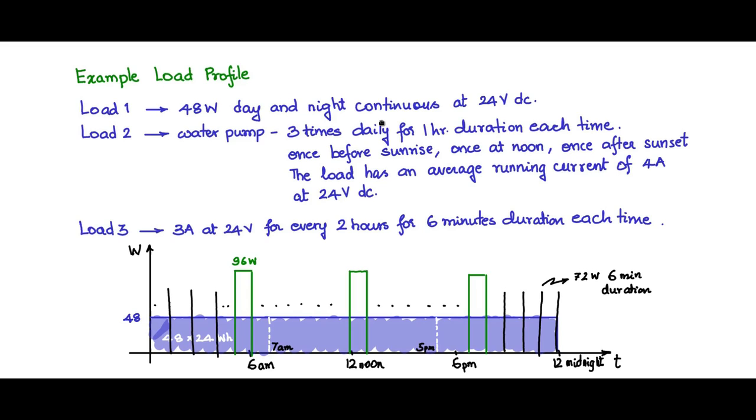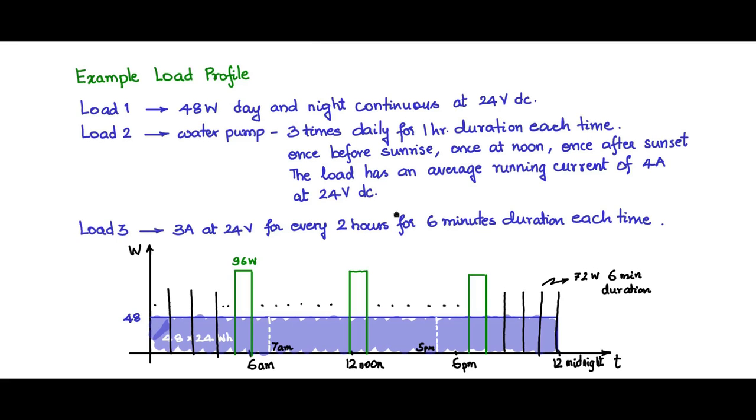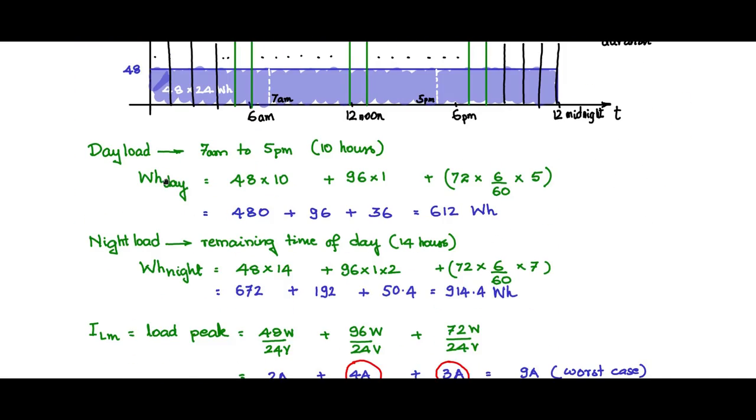For the example that we had discussed earlier, recall that it had three loads. Load 1 was a continuous 48 watt day-night load, 24 volt DC. Load 2 was a water pump, three times daily, one hour duration, again 24 volt DC. And load 3 was 3 ampere, 24 volts, every 2 hours, for 6 minute duration. We had the day load of 612 watt-hours and the night load of 914.4 watt-hours. Let us use this value for selecting the battery.